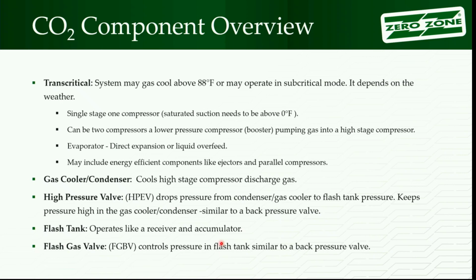So a lot of times we do sizing of valves. You're looking at, well, what do you size the expansion valve? What's the pressure drop going to be across it? We're looking at what you think your receiver tank pressure is going to be compared to your evaporator. Usually it turns out 100, 125 pounds. But that's what it's doing. That valve is there to make sure there's a pressure differential to feed the evaporators in the system. Get it into a tank if you're doing a pump system or getting it through the expansion valves.